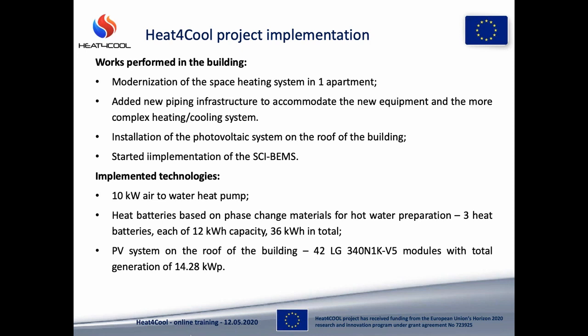The implemented technologies are a 10 kilowatt air-to-water heat pump, and heat batteries based on phase change materials for hot water preparation, 3 heat batteries, each of 12 kilowatt hours, 36 kilowatt hours in total. Photovoltaic system on the roof of the building, 42 LG modules, total generation of 14.28 kilowatts peak capacity.